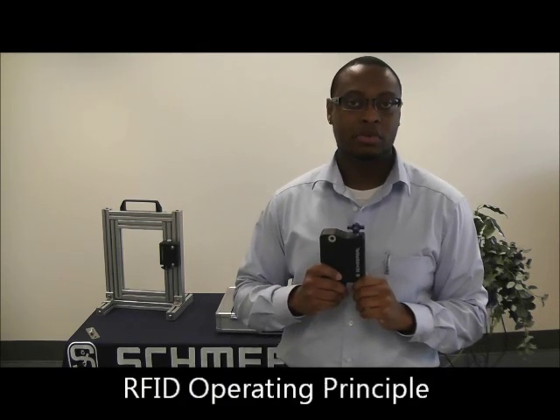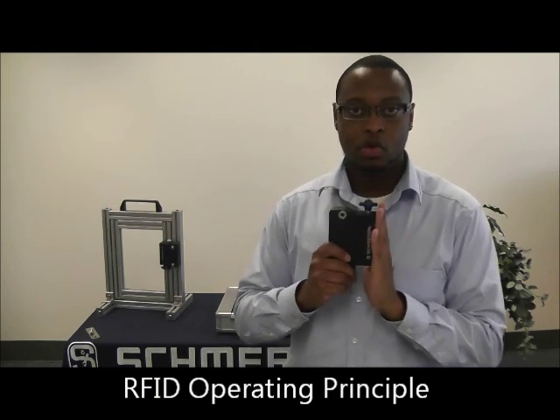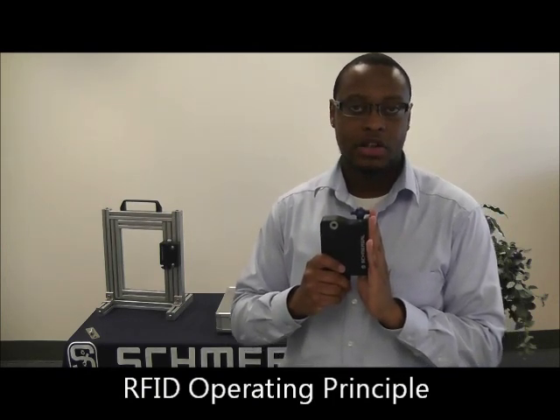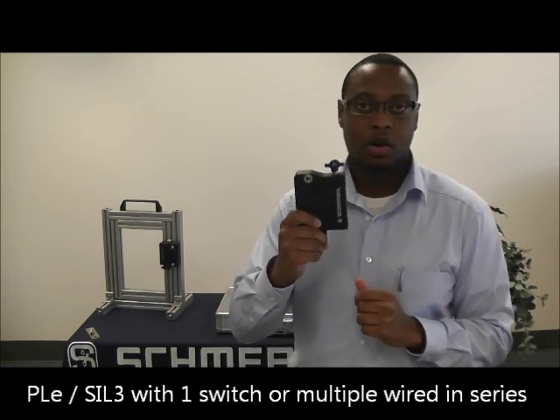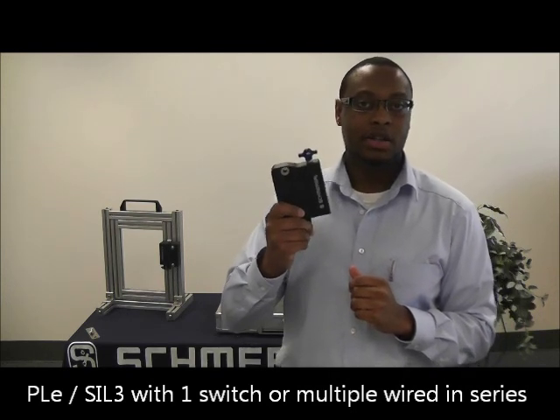The AZM300 is a safety interlock switch with a guard lock-in. It is based off the RFID operating principle, and it will include dual microprocessors for self-monitoring, self-diagnostics. That means that it can achieve performance level E, SIL 3 with just one switch, or other AZM300 wired in series.